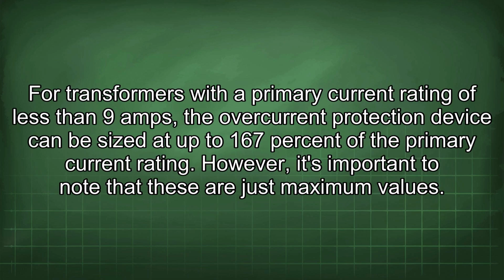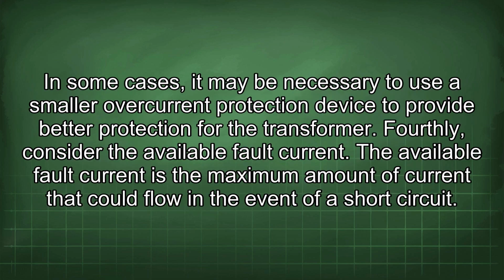For transformers with a primary current rating of less than 9 amps, the overcurrent protection device can be sized at up to 167% of the primary current rating. However, it's important to note that these are just maximum values. In some cases, it may be necessary to use a smaller overcurrent protection device to provide better protection for the transformer. Fourthly, consider the available fault current.